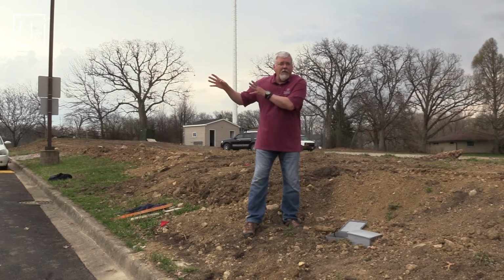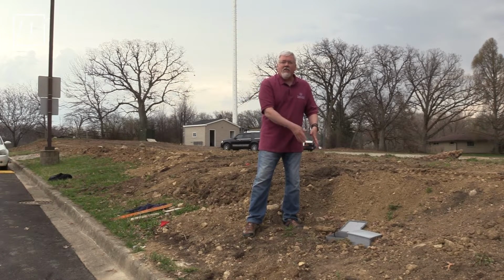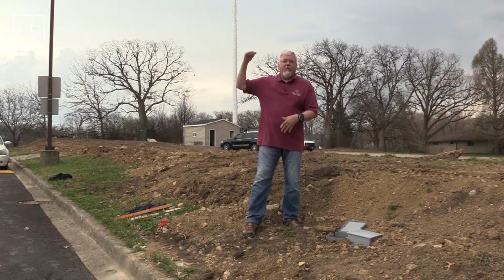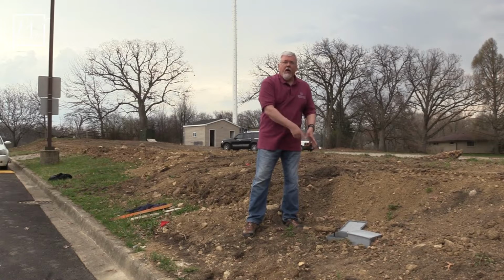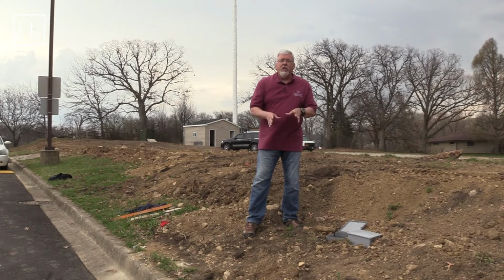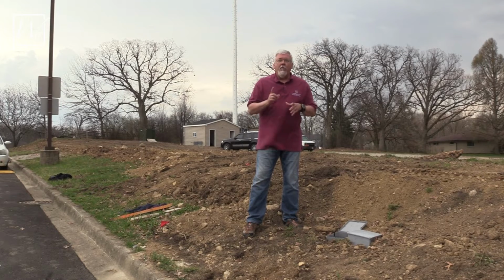So the wire from the sensor actually lands in this box. We're going to supply the wire to get from that hut over to here. Make sure you follow the instructions on what size wire to use at what distance. Also, make sure you remember to do your voltage drop calculations for the high voltage wire feed.